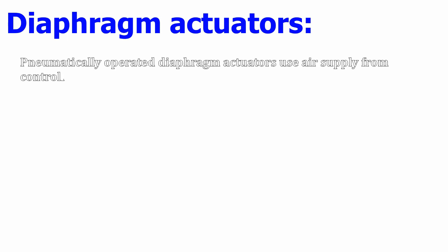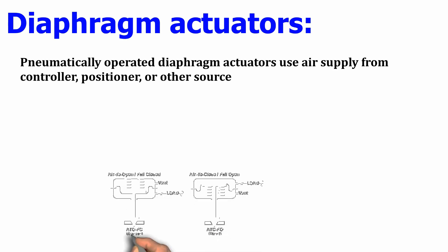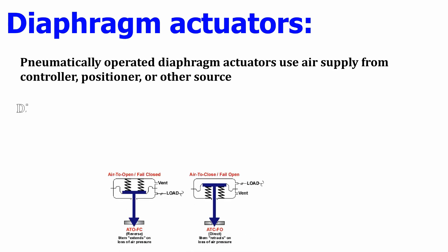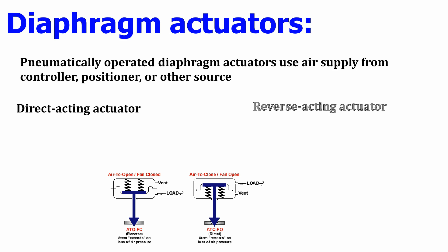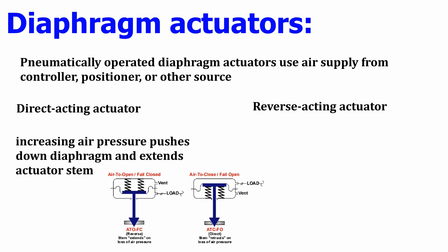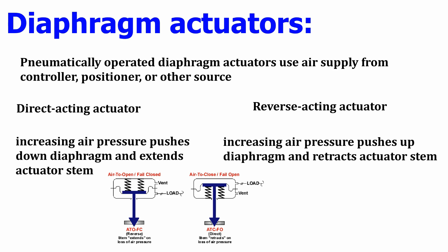First and foremost, what is a diaphragm actuator? Diaphragm actuators are pneumatically operated using air from a controller, positioner, or other sources. They are classified into two types: direct acting and reverse acting. In a direct acting actuator, increasing air pressure pushes down the diaphragm and extends the actuator stem downward. In a reverse acting actuator, increasing air pressure pushes up the diaphragm from the bottom, thereby retracting the actuator stem.